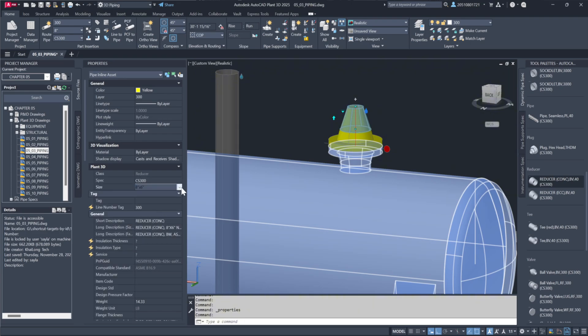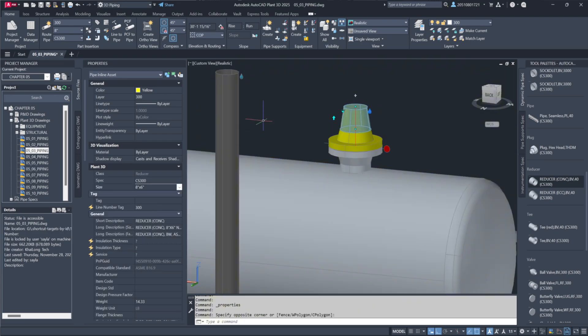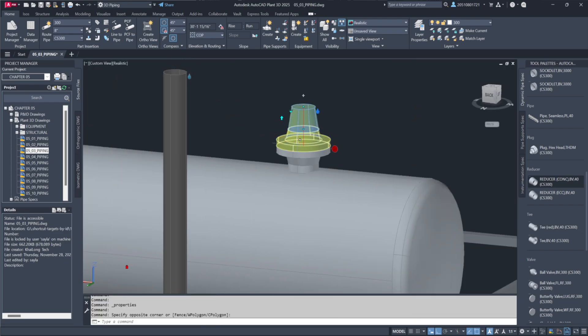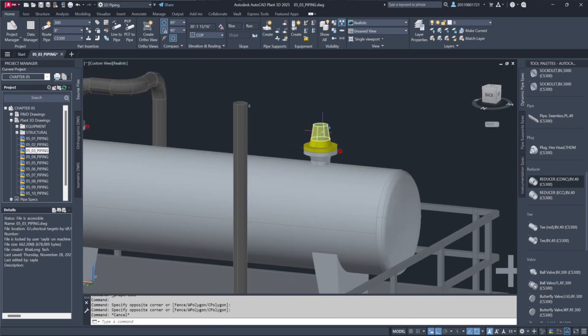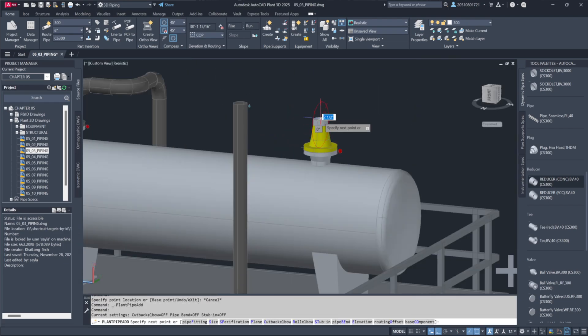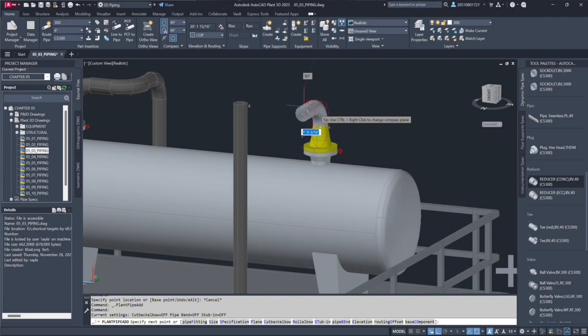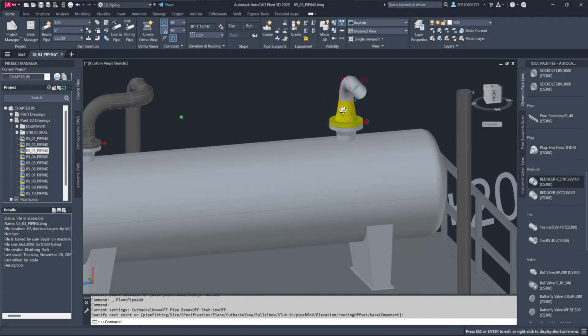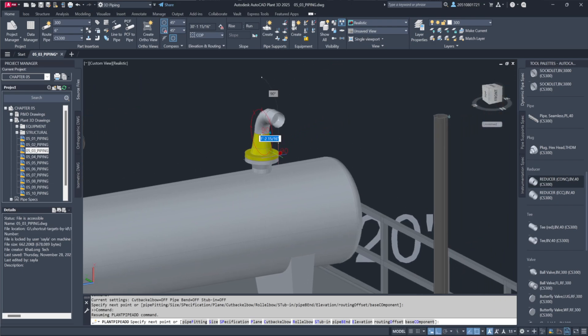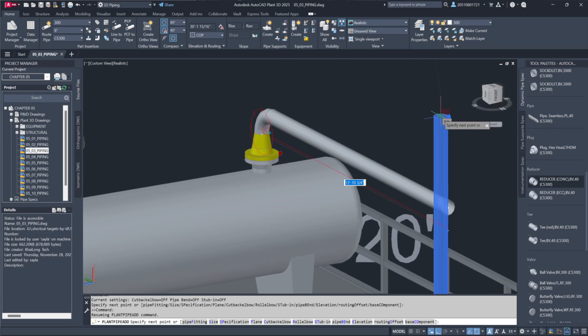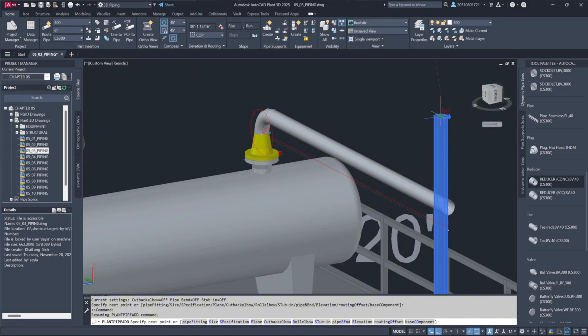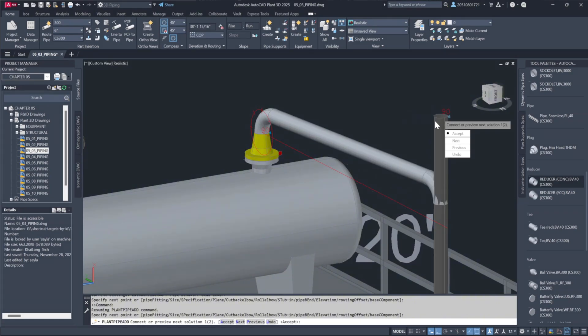Next, I'll demonstrate the AutoRoute feature. It's useful for simple routes, though I recommend verifying the results. I'll start by continuing the pipe at 6-inches with a 150-pound rating. Instead of calculating the distance manually, I'll let AutoRoute handle it. I'll pull the pipe up, select the node on the top of the pipe, and let Plant 3D generate a suggested route.